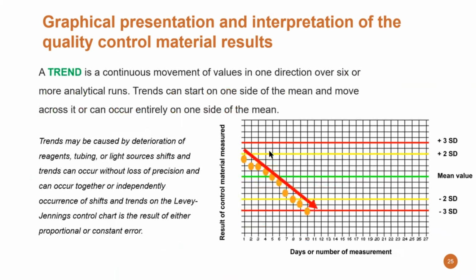Another situation might be a trend. A trend is a continuous movement of values in one direction over 6 or more analytical runs. Trends can start on one side of the mean and move across it, or can occur entirely on one side of the mean. Here in the graph you see that the values are moving downwards and reaching the 3SD limit.